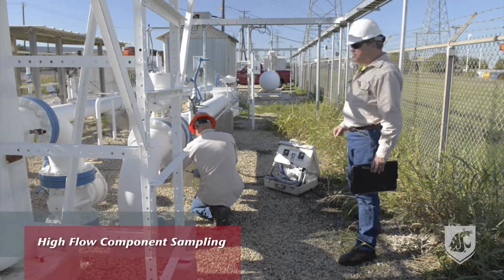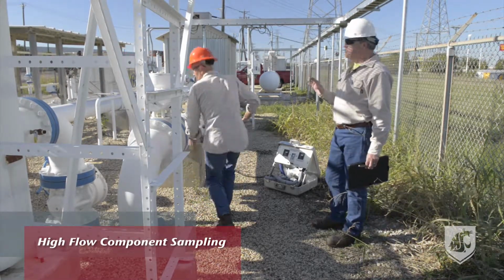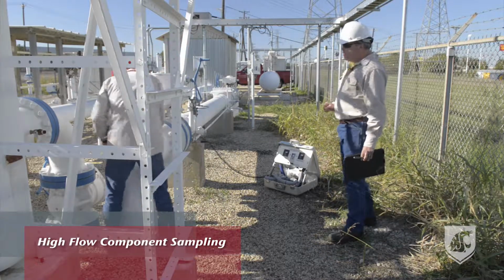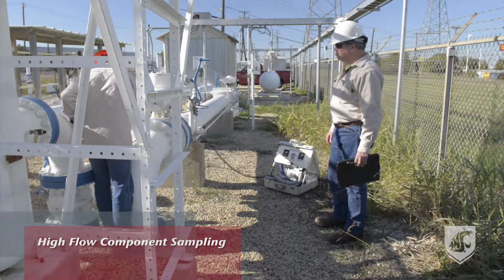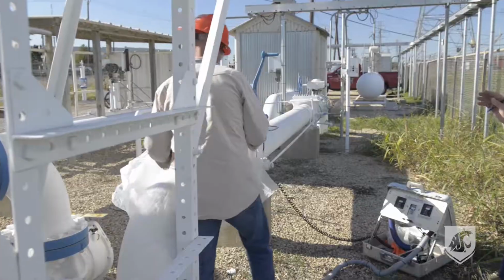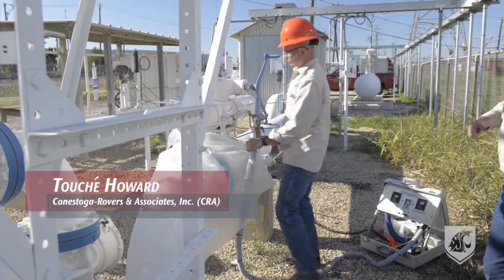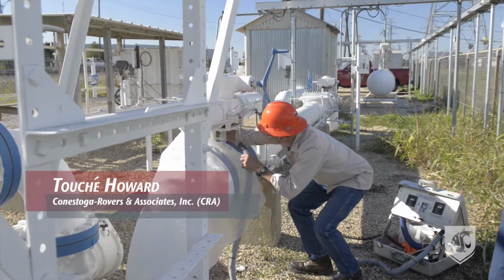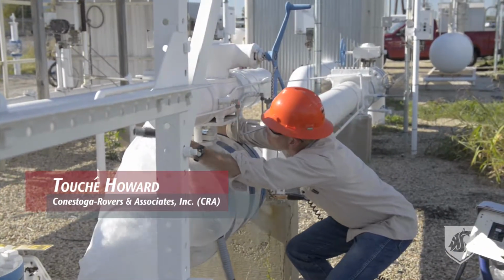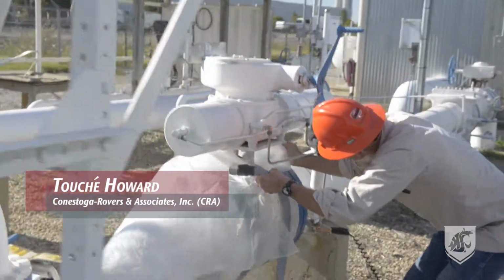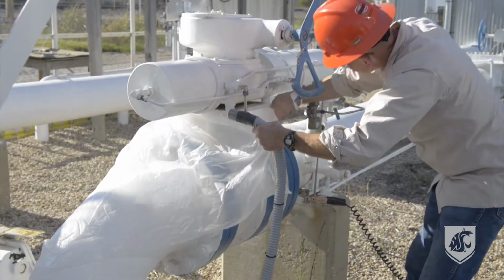Okay, so the first step in the process is to screen each of the components at the facility looking for methane leaks. The screening procedure just tells you that there's a leak. It doesn't tell you how much gas is leaking. So the next procedure that we use is called a high flow sampler.